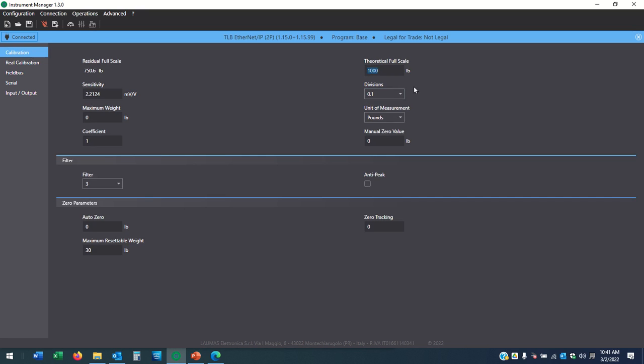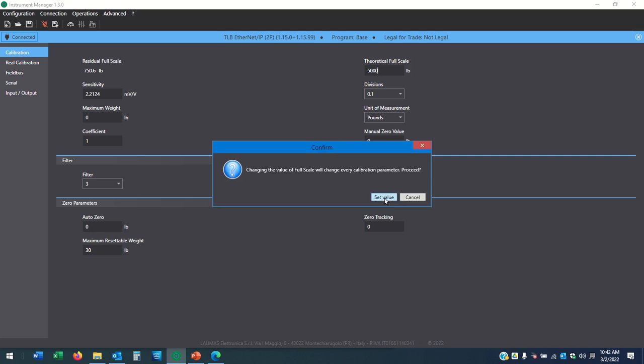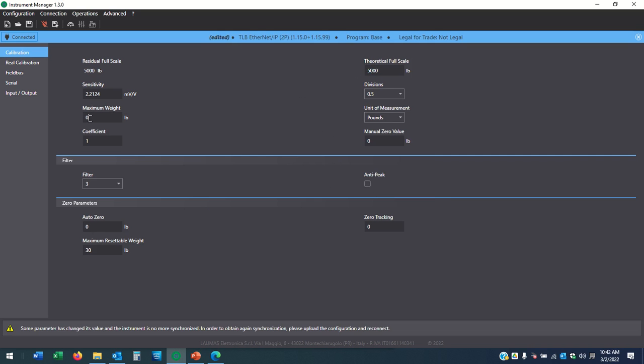I can tell it that it's 1,000 pounds. What's nice about this is that if I had one load cell that's 500, one that's 5,000, one that's 2,000, and I wanted to back up all of the load cells. If I had a 5,000 pound load cell, I can make that 5,000 pound load cell run like a 200 pound load cell, or a 1,000 pound load cell, or a 2,000 pound load cell, or anything I want. So let's say that I've got a full 5,000 pound load cell. However, I wanted to make this maximum weight only 2,000 pounds. That means that even though it's a 5,000 pound load cell, I'm going to scale everything over 2,000 pounds.